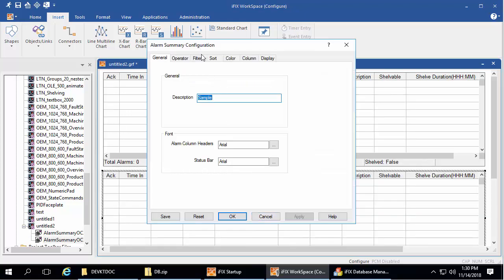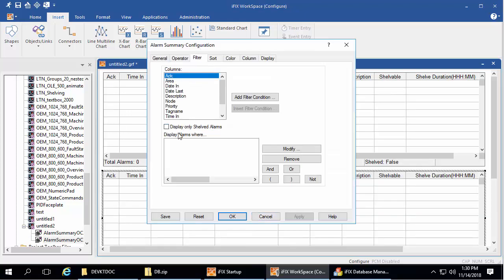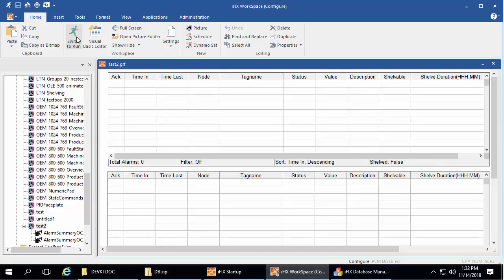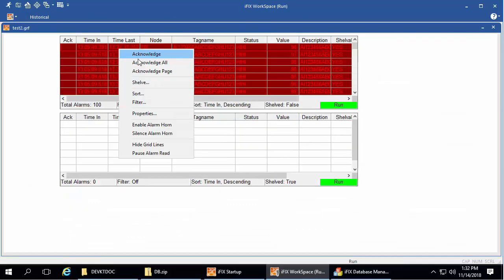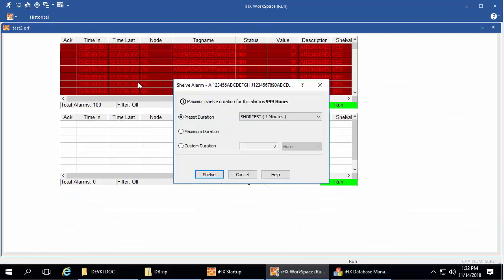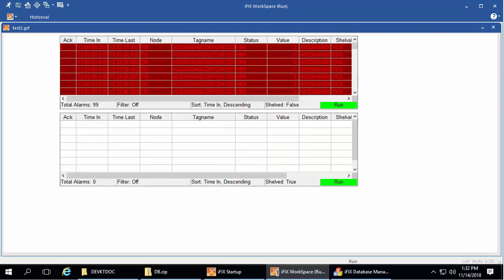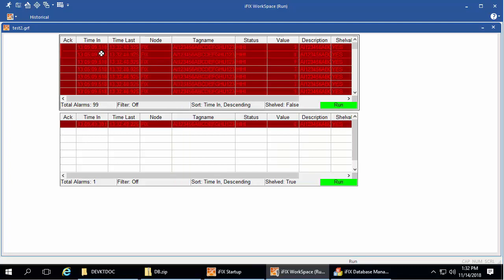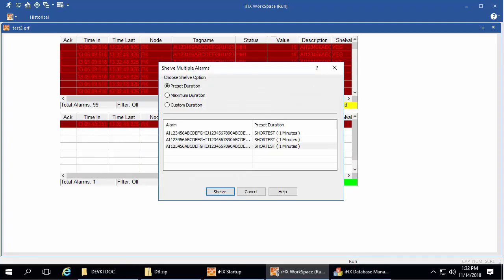On the filter tab, select this checkbox and click OK. When you move to run mode, from the alarm summary object, select the alarms you want to shelve from the right-click menu, and click Shelve. Select the duration, and then click Shelve again. You could select multiple alarms as well, and then click Shelve.